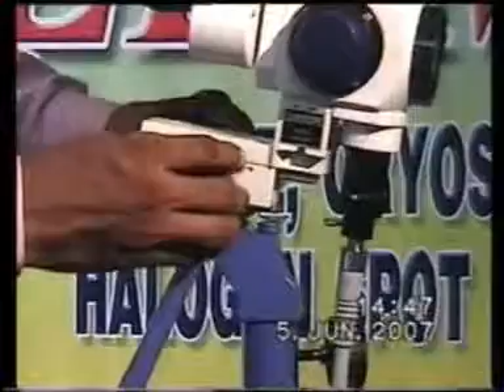Now the other portion here below the lens is called rack and pinion movement. It is for maintaining the objective lens distance. The focal length for colposcopy is approximately 30 centimeter, that is 300 mm. So that 300 mm lens is fitted. By mistake, if the objective lens distance is around 280 mm or 310 mm, this knob is to be adjusted, then it should be brought to 300 mm. The object, that is the cervix, should be kept exactly at 300 mm. Then only you will get the focusing in the lens.